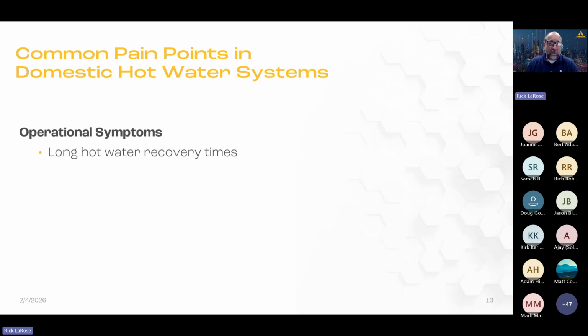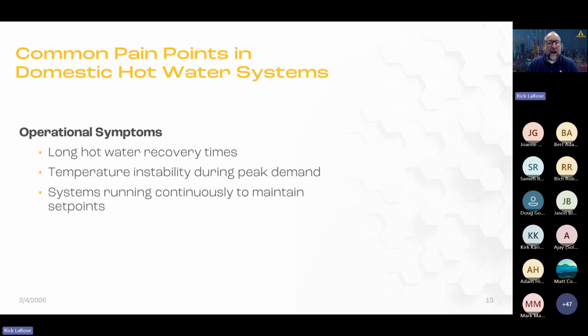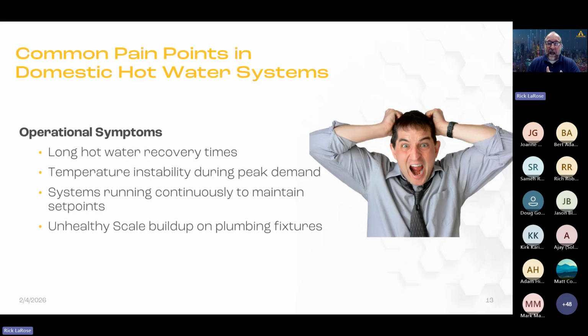So again, when that scale starts to build up, you get long recovery wait times for hot water and temperature instability. And when that scale builds up on heat transfer surfaces, like in your plate and frame heat exchangers or tube and shell heat exchangers, you're going to need to do clean-in-place with an acid or rid-lime solution, or you're going to be replacing tube bundles.